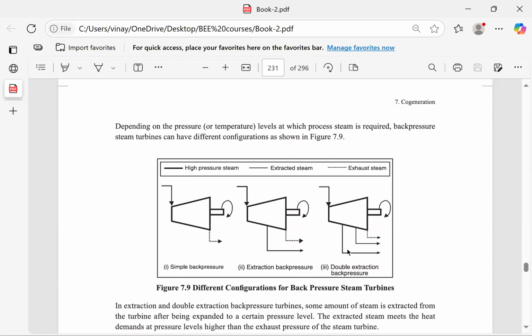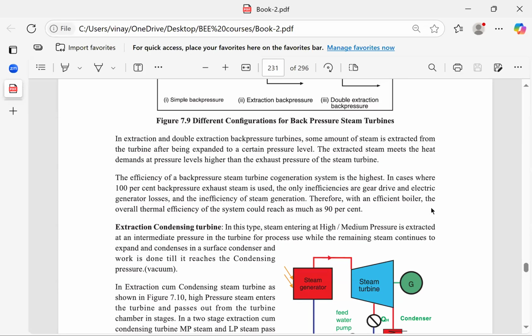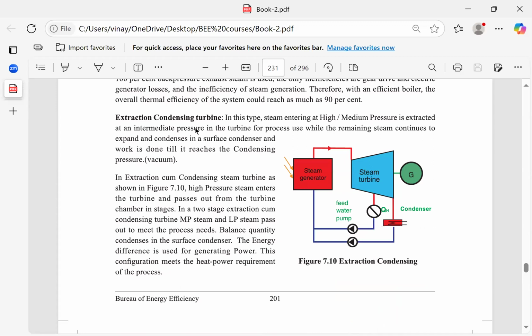If I am using double extraction, this is first extraction, higher; extraction 2, extraction 3. So we have the flexibility to get the steam at different pressures and temperatures as required by the process, right? With the extraction condensing turbine, as I said again, we may lose some heat efficiency, but we get better generating capacity, and partial steam is going for the process here.